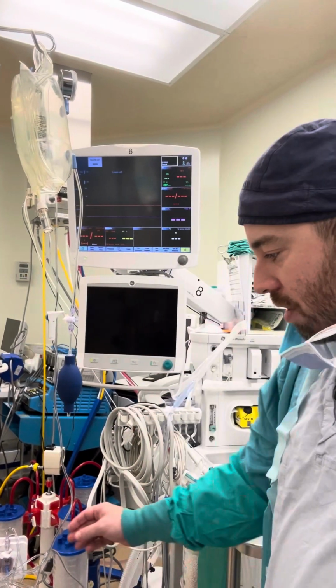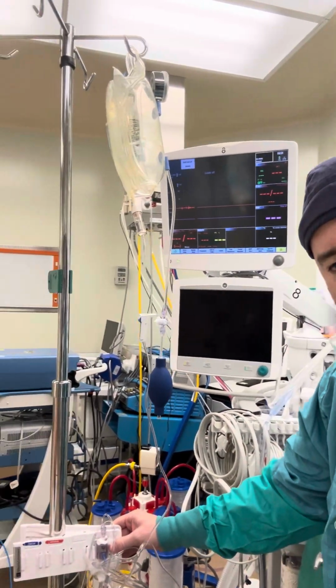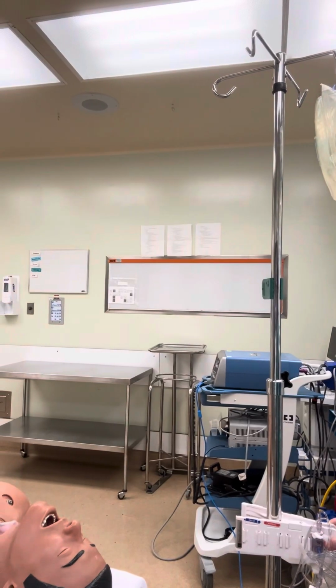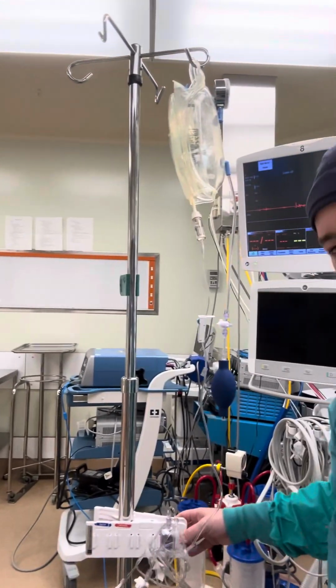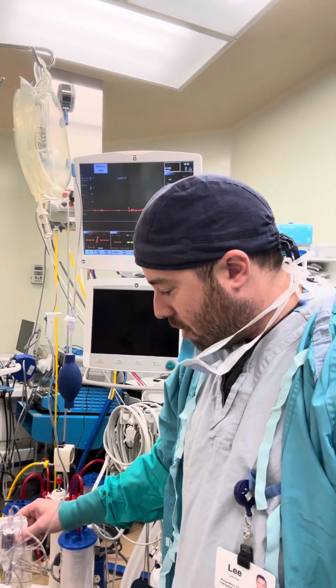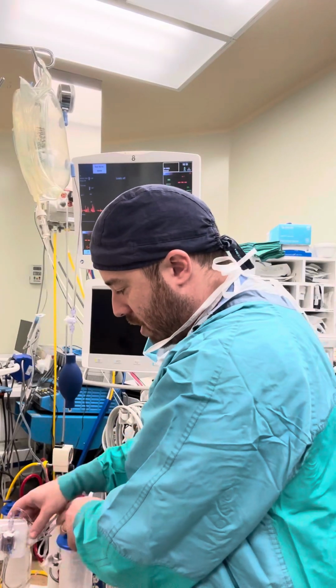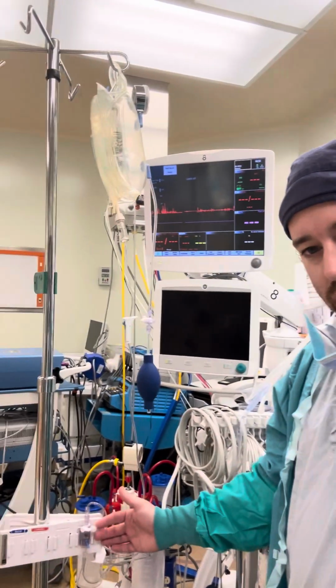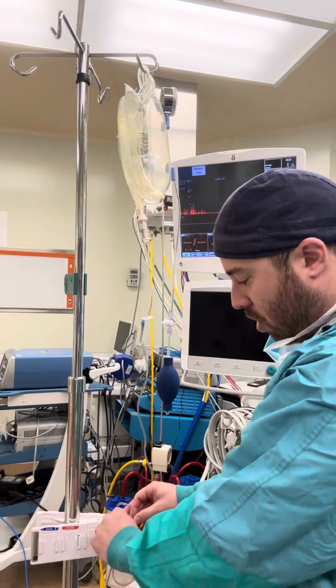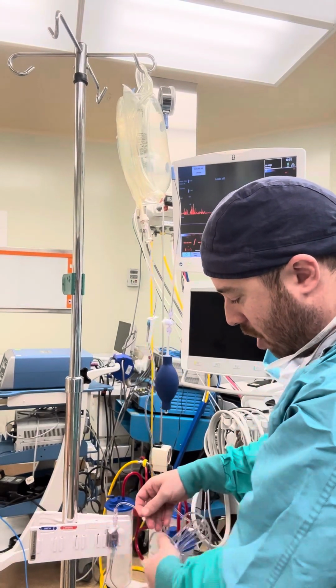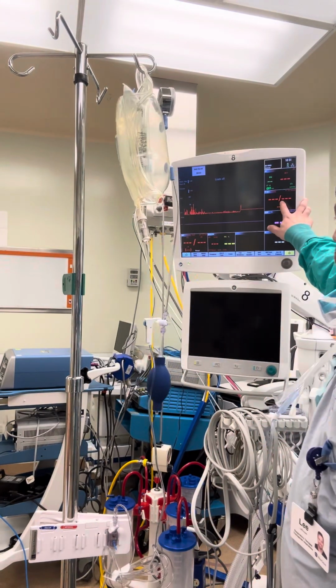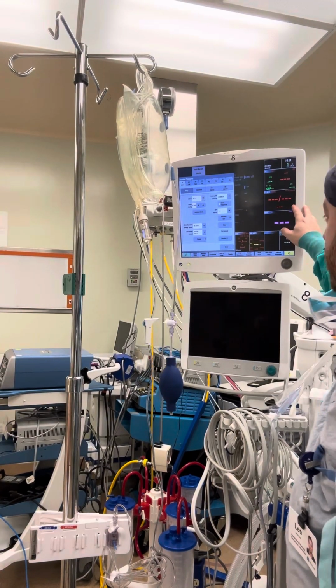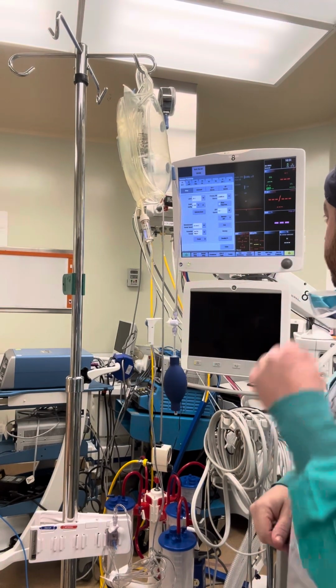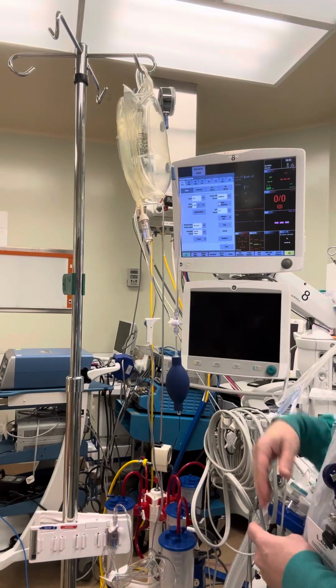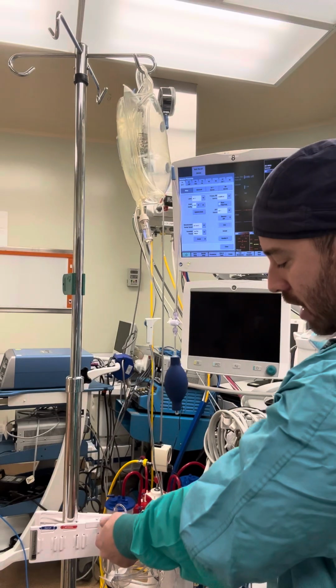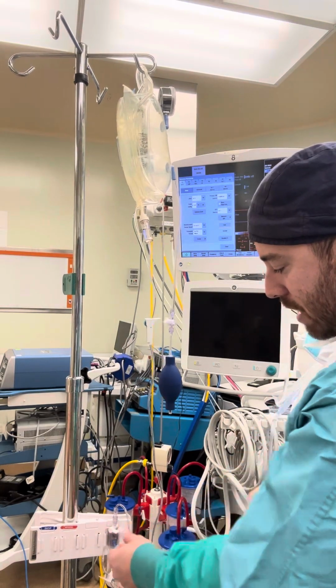So if you look here, what I've done is adjusted this to the phlebostatic axis of the patient. You can see that there, trying to fit it into the frame. Now, this transducer fortunately has an open air cap, so all we really need to do is turn this off to the patient. I'm going to go to our arterial pressure line here, and then I'm just going to zero that. As you can see, it's coming up and it's zeroing. Now it is zeroed.